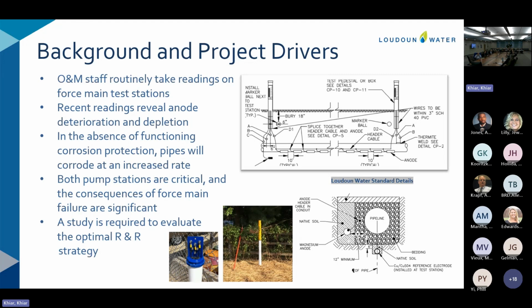Anodes are the foundation of the corrosion protection system. They sacrifice themselves to protect the pipe. Now that they are deteriorating, in the absence of a functioning corrosion protection system, the pipe will start to corrode. Both these pump stations serve a population that's quite critical, and the consequences of failure of these force mains are very high.